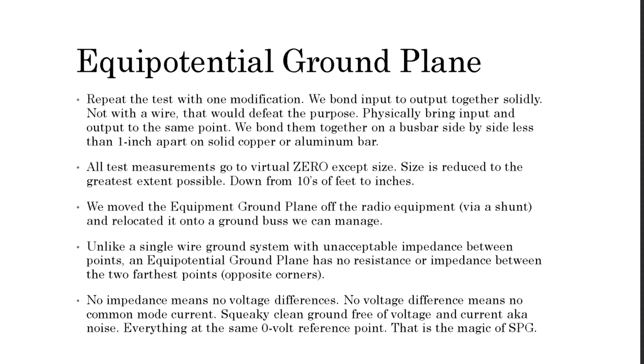So if we don't have any impedance, it means we can't have any voltage differences across that plane. And if we don't have any voltage differences, it means there's no common mode current flowing through any of our equipment. We got a squeaky clean ground system free of voltage and current. Everything is at the same 0 volt reference point. That's the magic of the single point grounding, and it's really no magic at all. It's just basic fundamentals.